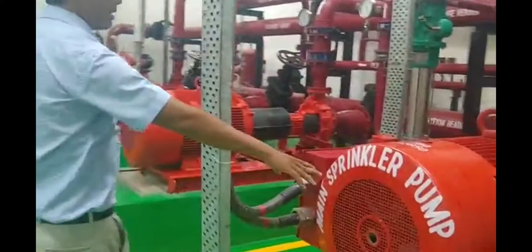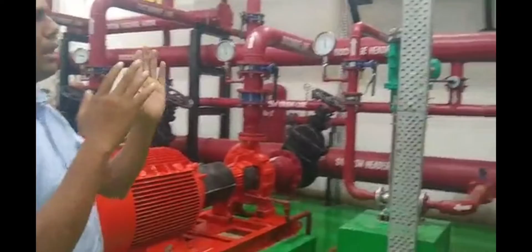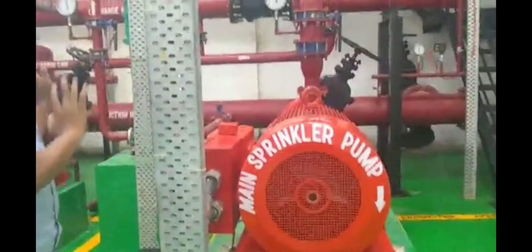Among the individual pumps, there is the sprinkler main pump, the hydrant main pump, a jockey, and an engine. There are two systems, the sprinkler and the hydrant system. We have kept the sprinkler system separate. The sprinkler system is not going to support the hydrant system, but there is an NRV. Whenever the sprinkler system requires it, the hydrant pump can support it.